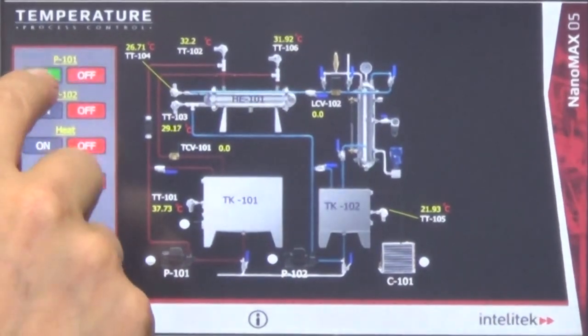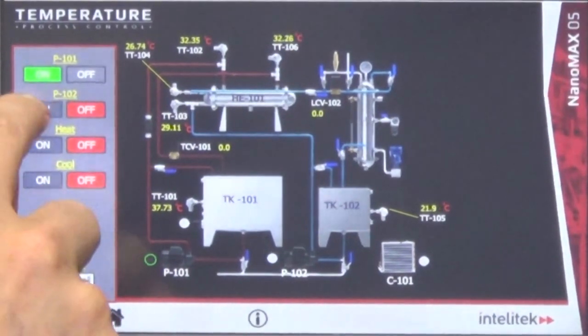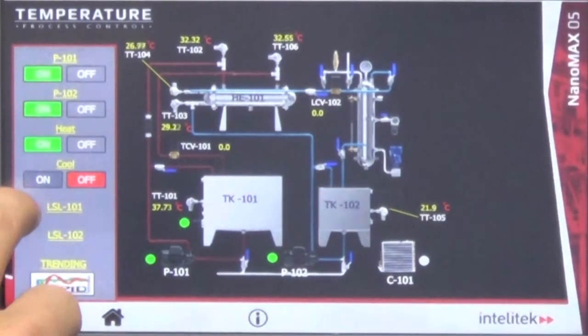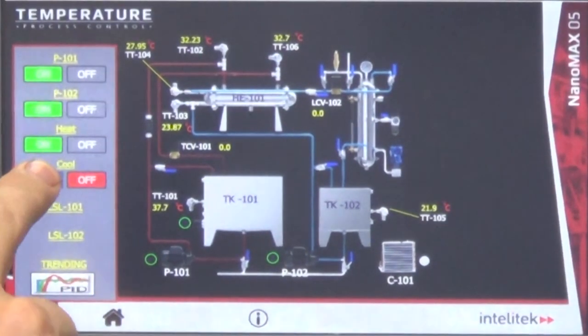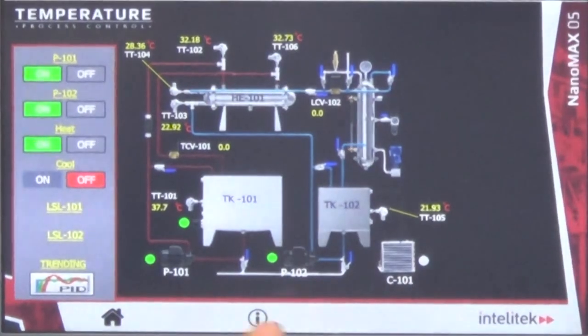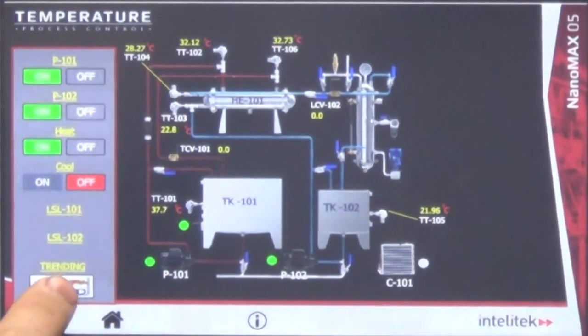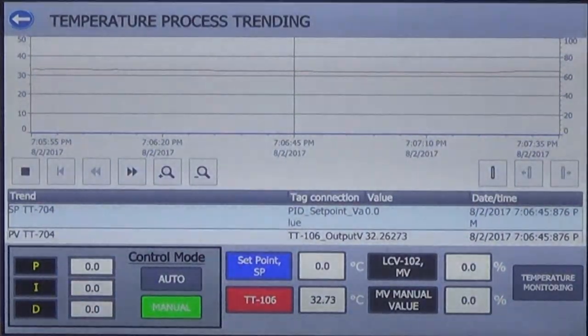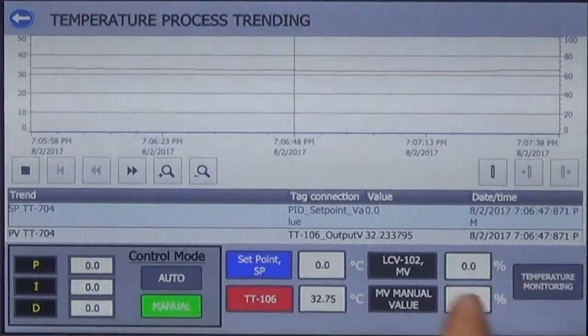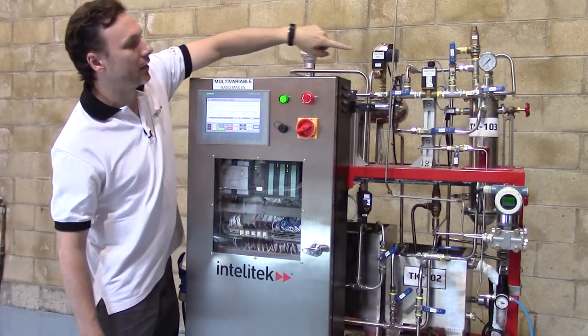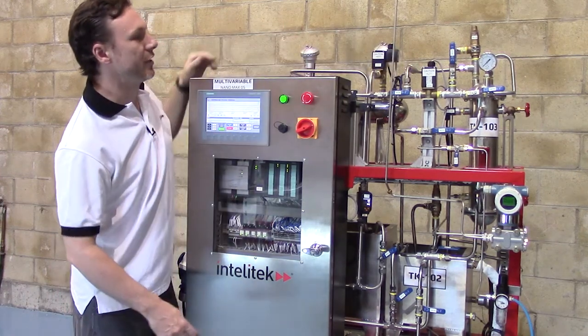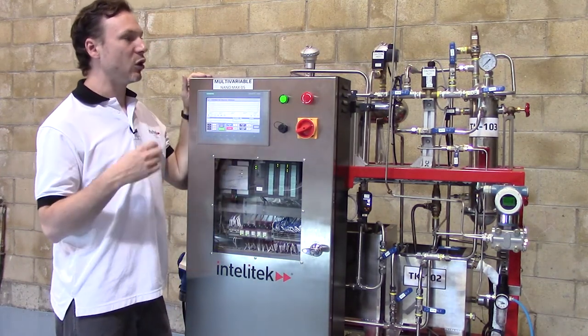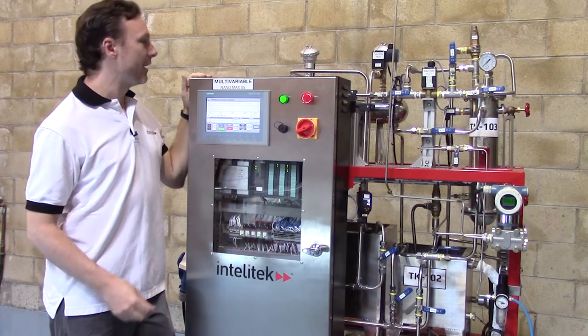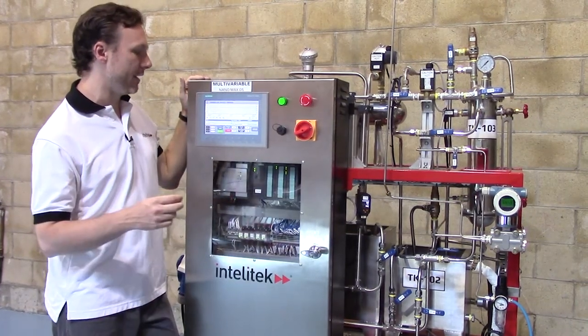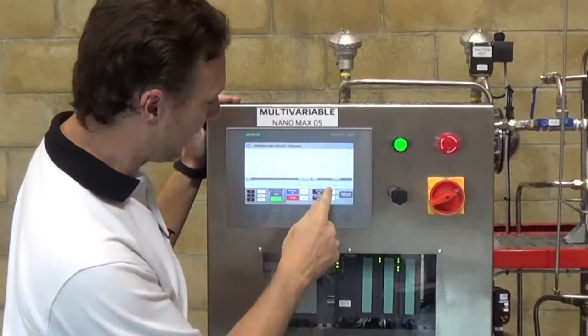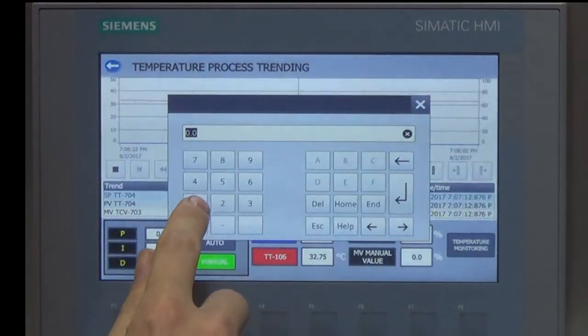So I'm going to turn on pump 1, pump 2, the heater, and the cooling unit. Actually, the cooling unit's already at temperature, so can't turn that on. And then I can again manually adjust the valve. The valve being controlled is this one right here, and it's basically determining how much cold water, at what rate, is being exchanged through the heat exchanger. So if I open that up, I can cause the water temperature to adjust.